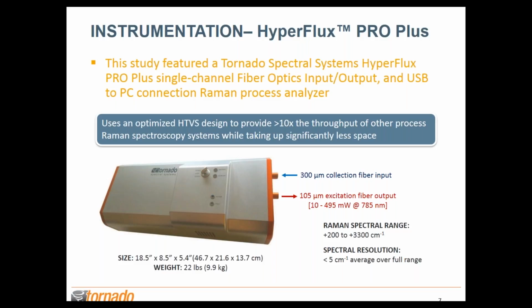The laser power is configurable between 10 to 495 milliwatts. We decided to have a maximum of 495 to ensure that the laser power does not exceed 500, which keeps it a Class 3B system. Above 500, we then have a different laser classification of Class 4, which has different requirements that one would have to be concerned with.